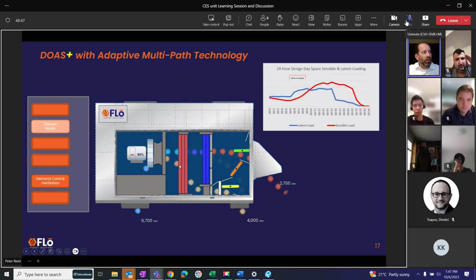We do use this coil at times to also add or temper the air, because sometimes there's just so much dehumidification going on, we can't temper it enough with our bypass, in which case we need to lift that temperature a bit. So we have that there as a tool in our toolbox. Our fan speed has increased to 80% in this case, and you'll see that through these different modes, our fan speed will change. The reason it's changing is as we adjust these dampers, we're changing the static pressures within the unit, because we have different channels the air is flowing through.